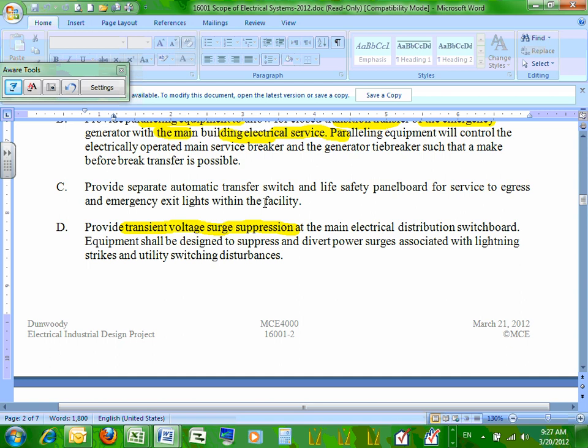And oftentimes I've seen this over here on the next wall, and you've got 25 feet of wire. It's pretty well useless in terms of being able to be a transient voltage surge suppression device. There's just too much line impedance between the busing that it's trying to protect and the component on the other wall.